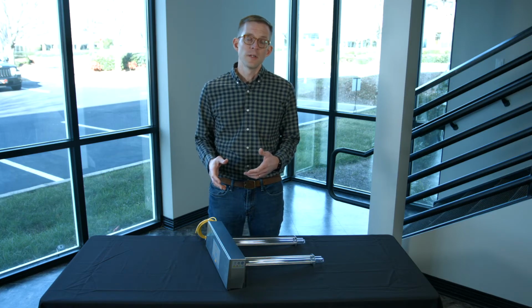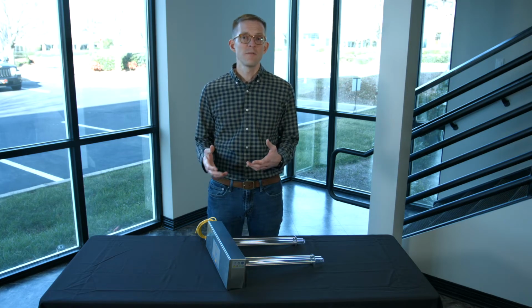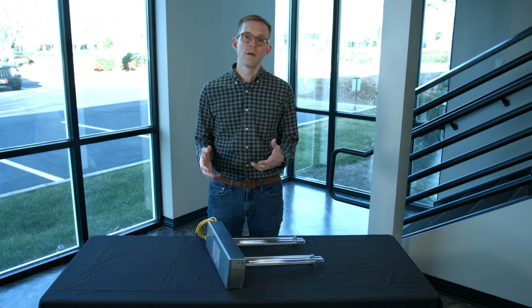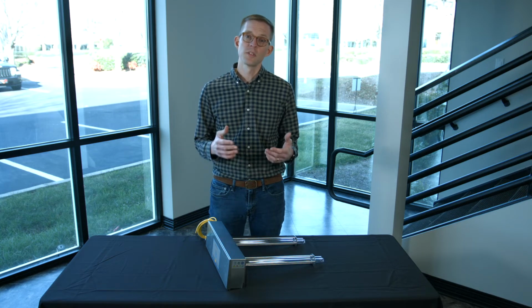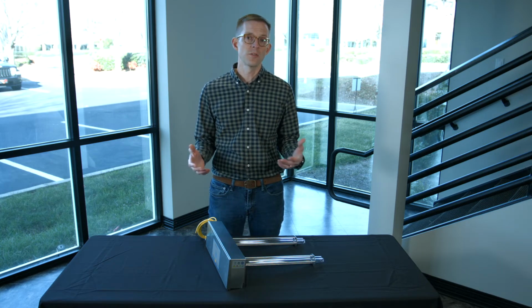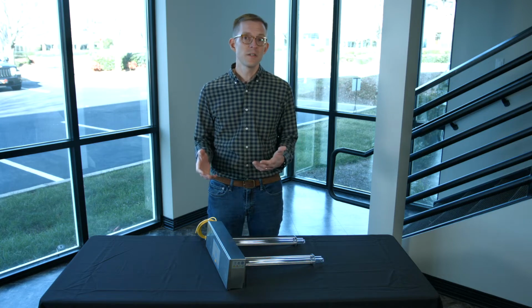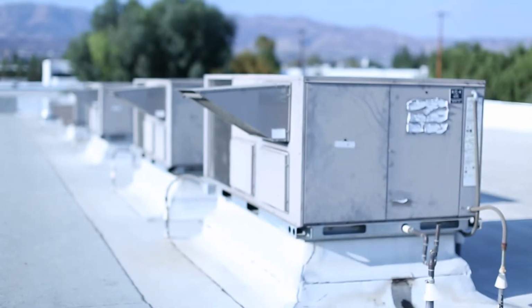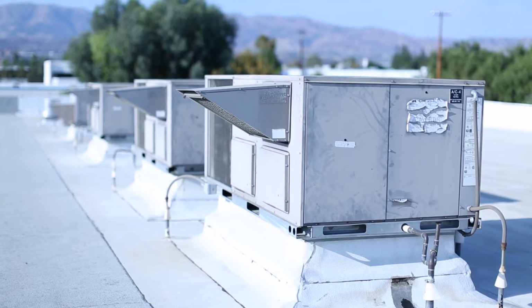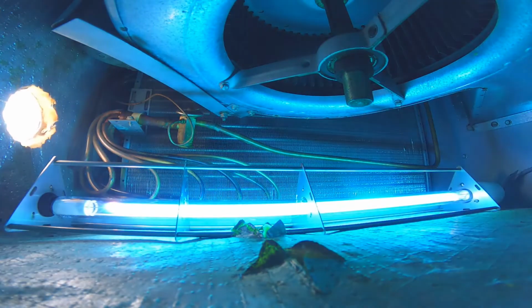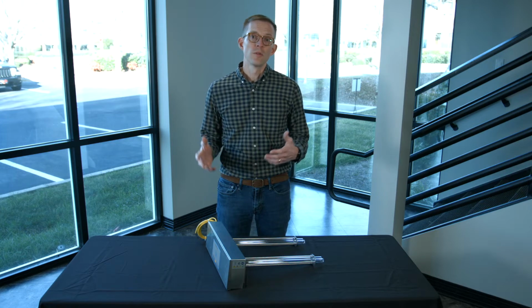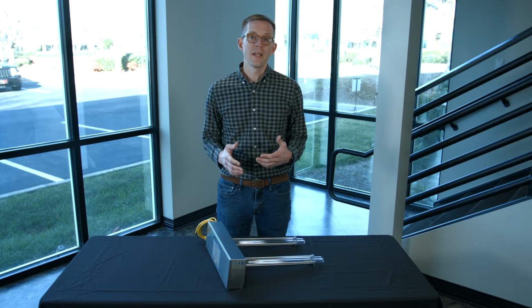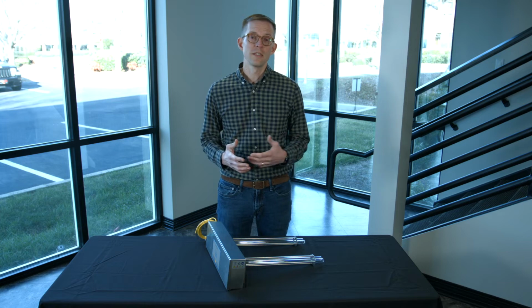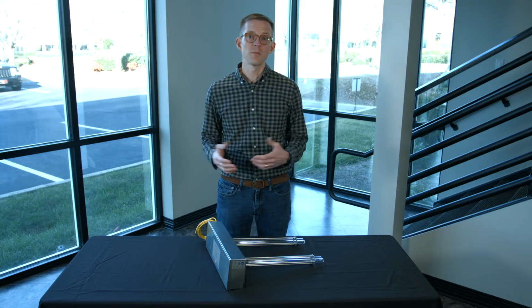The UV duct fixture is important because it's specifically targeting disinfection of the air as it's carried through the supply ductwork before any branches come off the system. This is different than UV lights that might be installed inside an HVAC cabinet or on-coil UVC applications. This is a great way to reduce pathogen load and ensure that air that's coming through the HVAC system is as clean and healthy as possible.